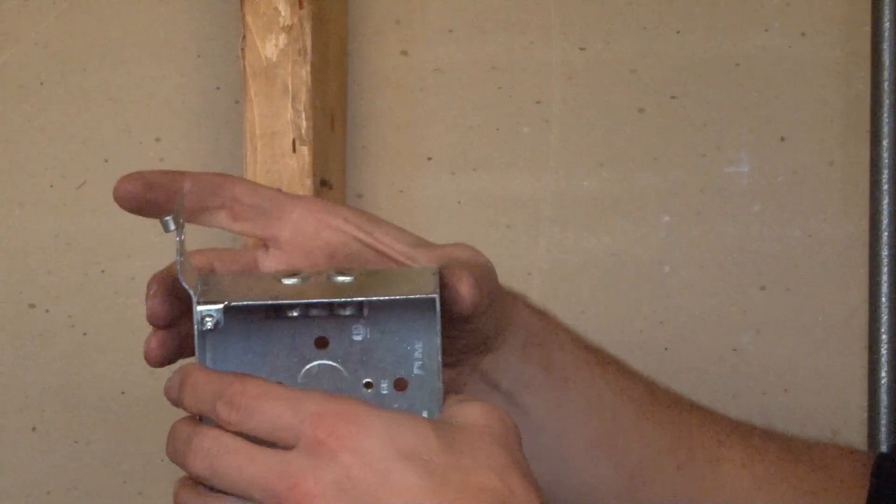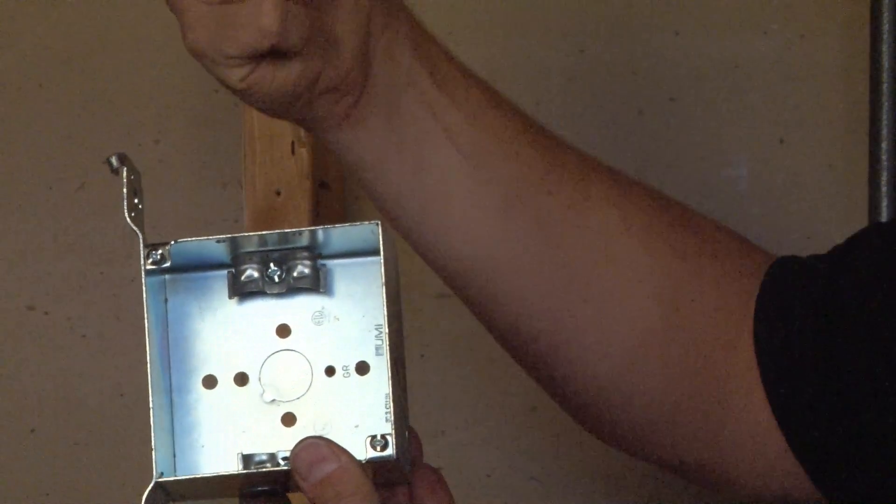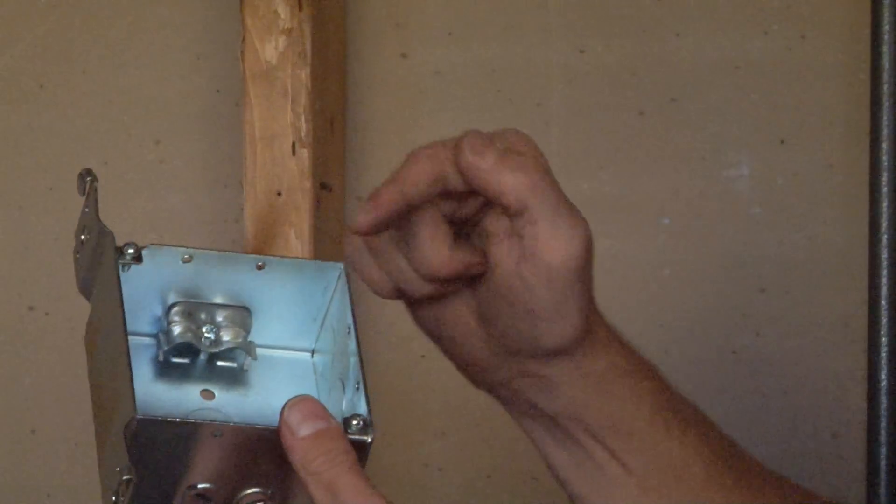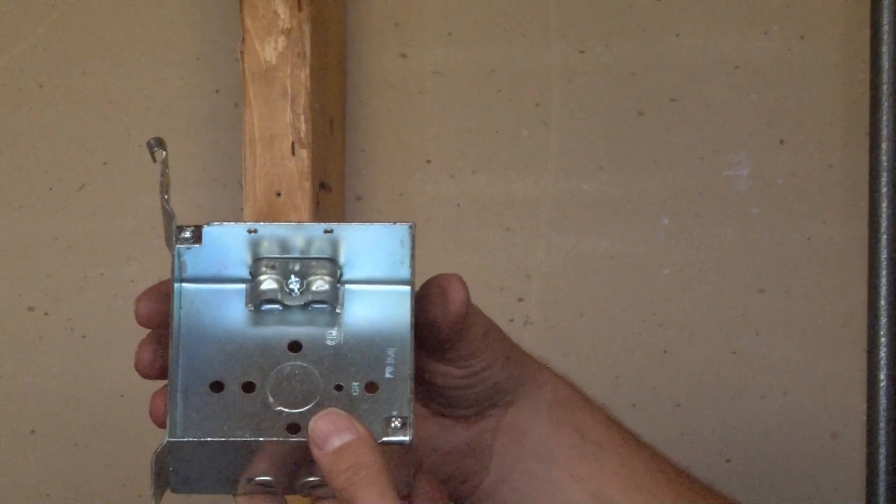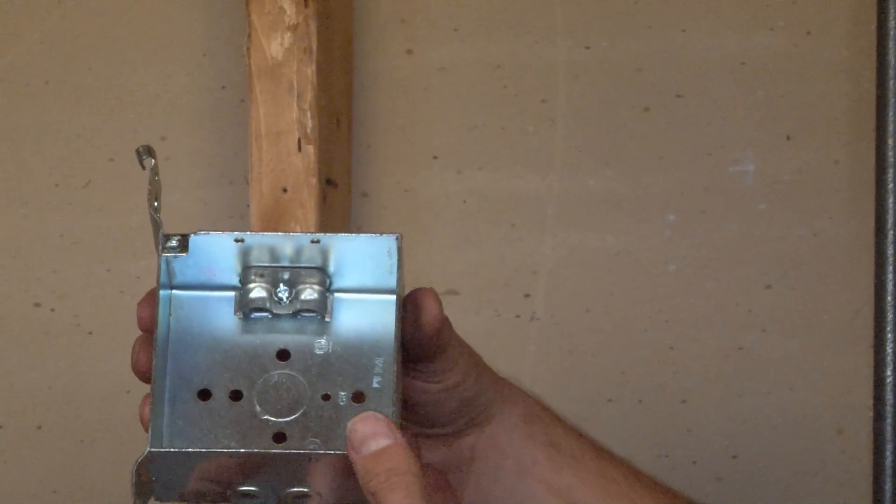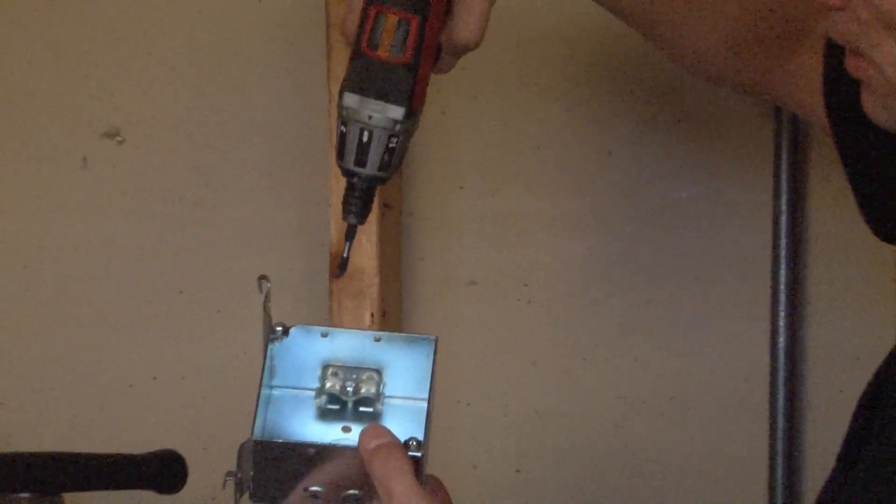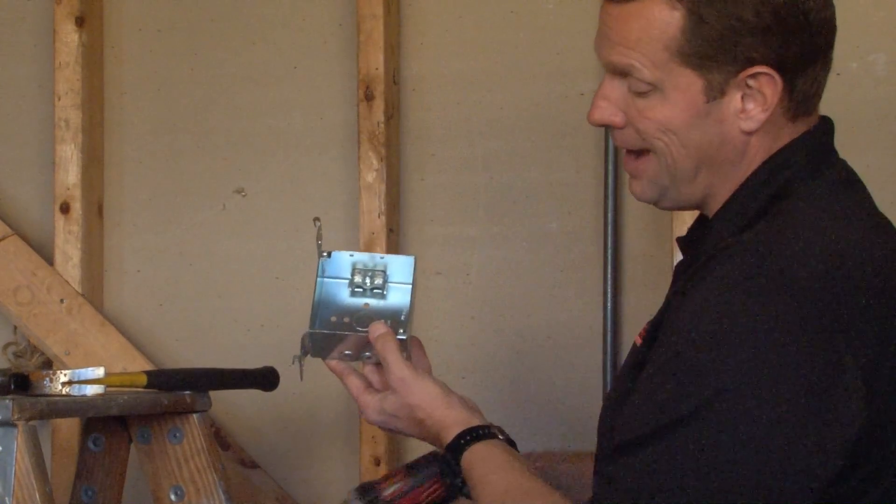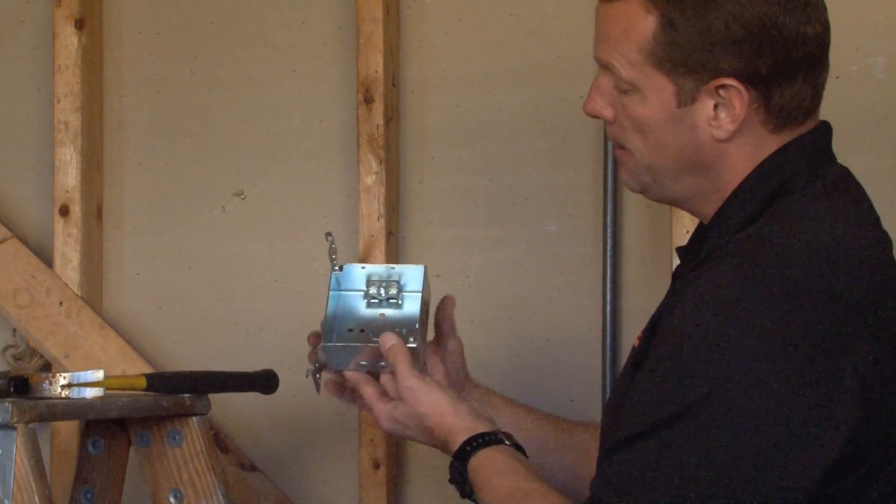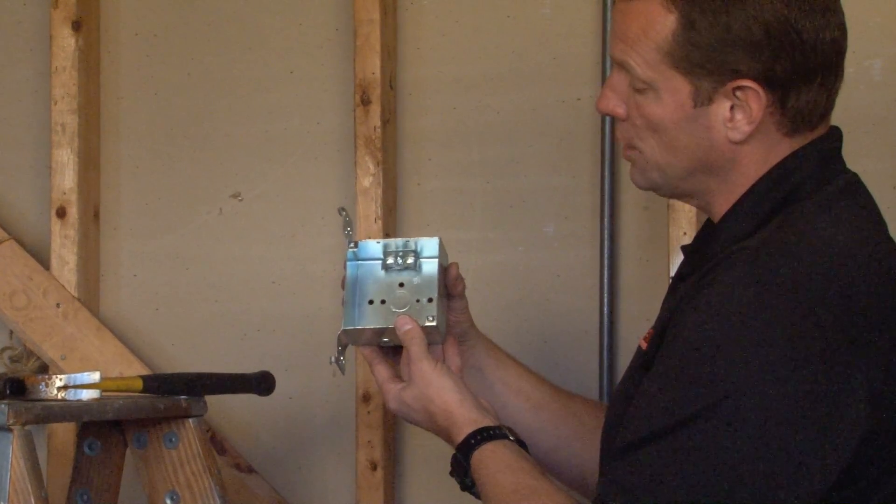Once the tab is removed, your non-metallic sheath cable is inserted into the hole and pulled right through the clamp in the bottom of the box. The installer can then screw down the clamp, thereby securing the cable in the bottom of the box so you don't need any external connectors.